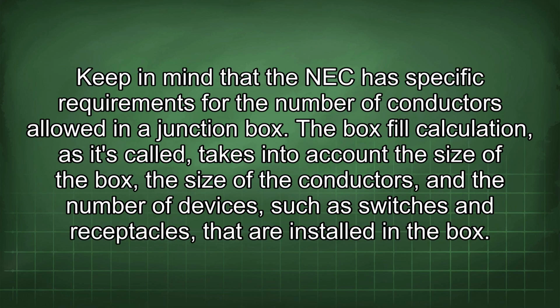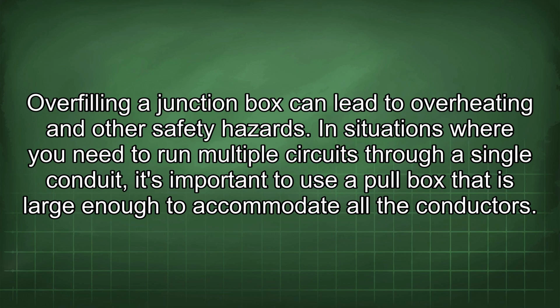Keep in mind that the NEC has specific requirements for the number of conductors allowed in a junction box. The box fill calculation, as it's called, takes into account the size of the box, the size of the conductors, and the number of devices, such as switches and receptacles, that are installed in the box. Overfilling a junction box can lead to overheating and other safety hazards.